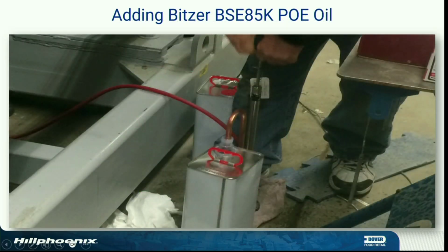So, everybody understands the old pump system. Me, I got a little trick. I used to take the cap and put it under the end of the can and tilt the can. That way I could get a little bit more oil out of it. Don't pump vapor into my system. And I actually watched a kid pump a gallon of oil into a reservoir that was at 515 PSI. I'll hire him right now. That guy's one strong guy. All right, so 45 minutes. I ain't messing with that guy. 45 minutes to get that can of oil in there. And when he was done and he was wiping the sweat off his brow, I go, you know, me, I would have went ahead and just vented it down to a little bit of pressure and then done it.